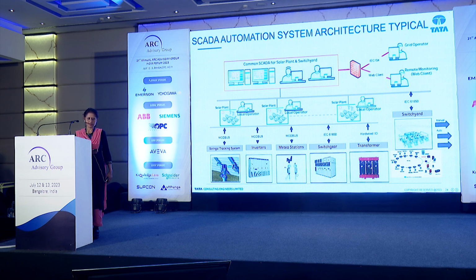This is a typical architecture of a Scada automation system in a solar power plant. Here we have the strings or tracking system for the panels, the inverters generally connected in the form of a daisy chain, the weather monitoring systems and soiling stations, the switchgear, transformers connected to operating cum engineering stations. The switchyard is also connected to the common Scada for the solar power plant and switchyard, and through a firewall it's connected to the grid operator, which is a mandatory requirement, and a web client which is used for remote monitoring and control.